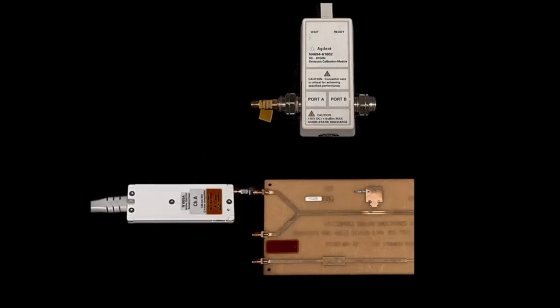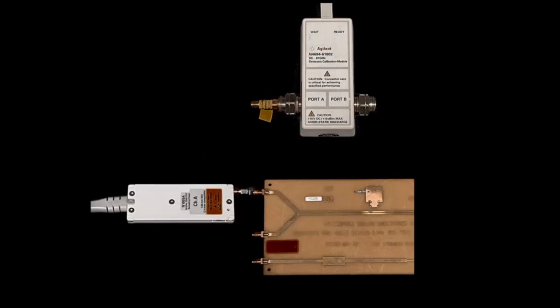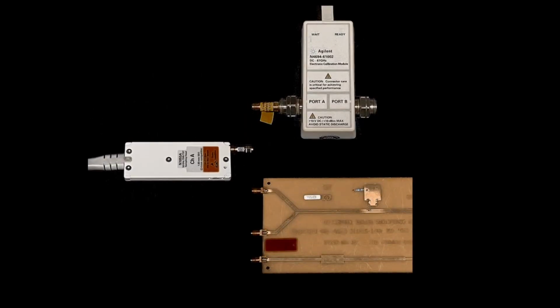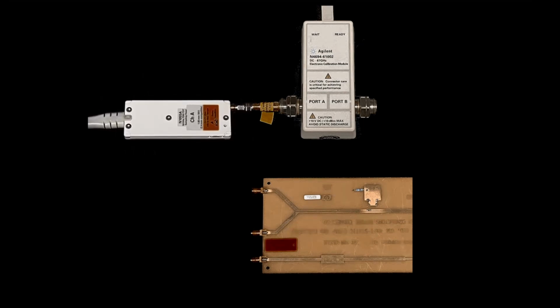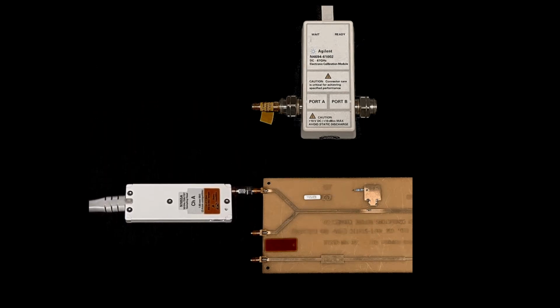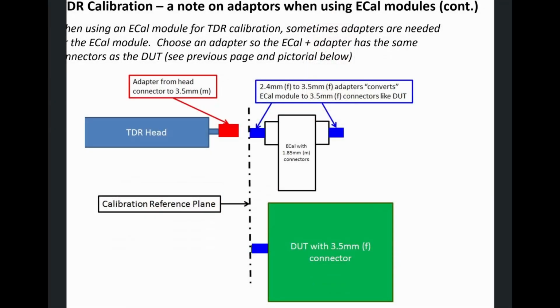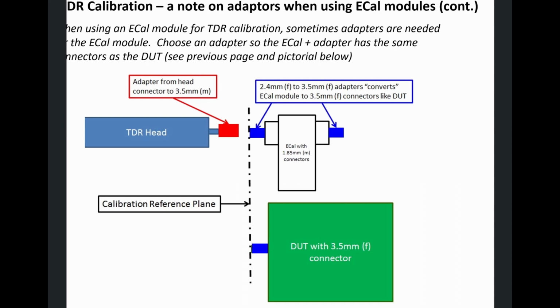The easiest way to look at things is to choose adapters for the Ecal. So the Ecal plus the Ecal adapter have the same connector as the DUT. That way, when you disconnect the TDR head plus adapter from the Ecal after TDR calibration, you can connect the TDR head plus the head adapter directly to the DUT without the need for any additional adapters. The calibration reference plane is at the end of the adapters on the TDR head and the end of the adapters on the Ecal module right here.